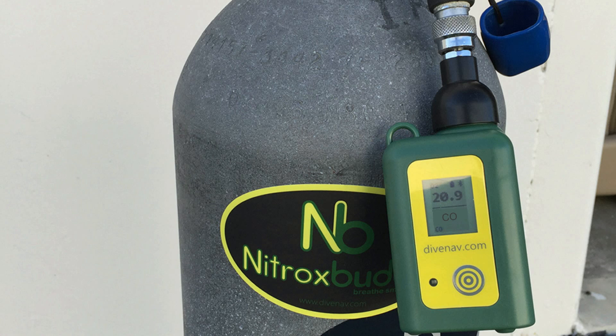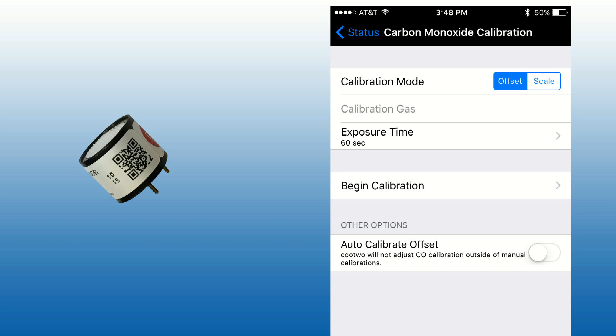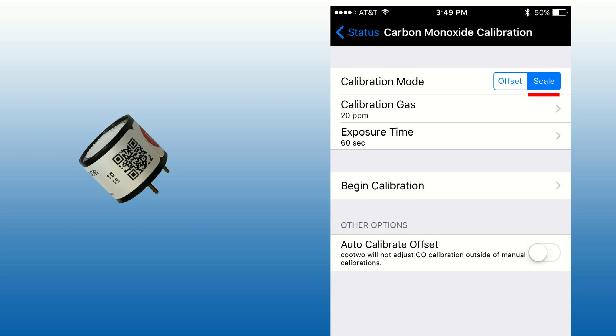To perform the carbon monoxide sensor scale calibration, select Scale. Then select the value of the reference gas — either 10, 15, or 20 ppm.